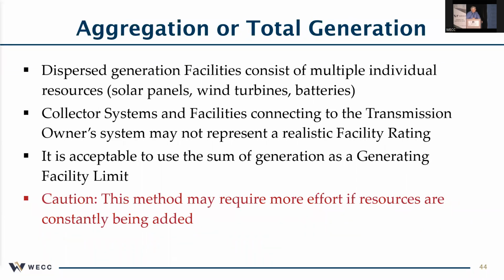The last thing here is for aggregation or total generation. And this is one that came up. It kind of relates to the prime mover issue in a way, but there's an emphasis on facility ratings for series components. But we all know in the case of wind farms, dispersed generation in general, that you have these strings of elements out there that are generating, and then they go together and they go to feeders. The collector system is designed with a certain rating, and then you have the generators down there providing it.